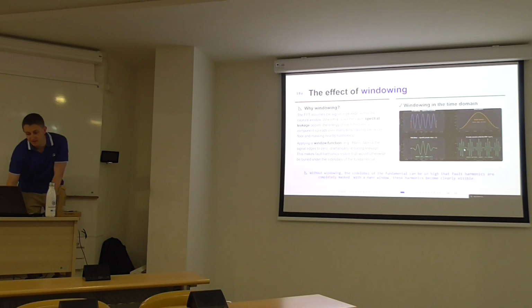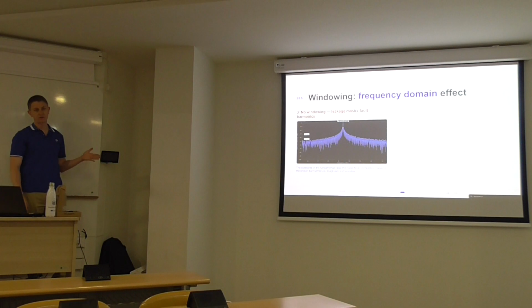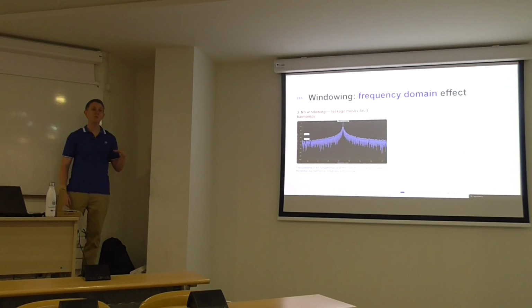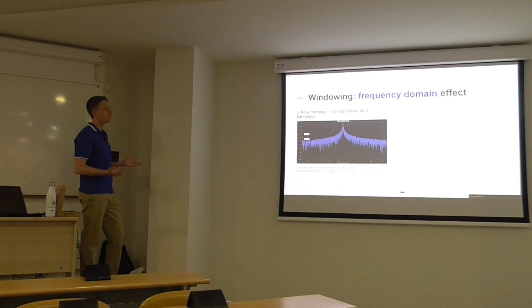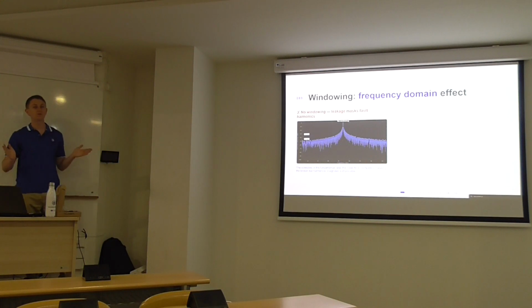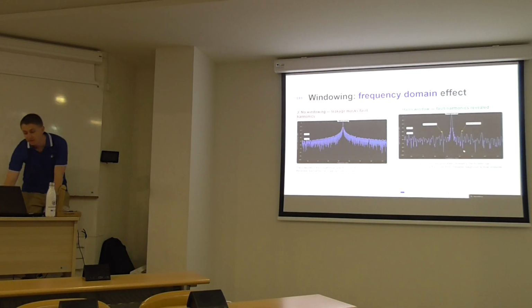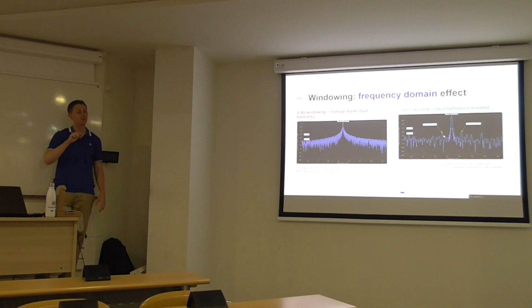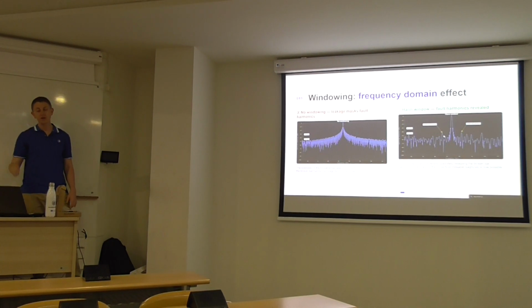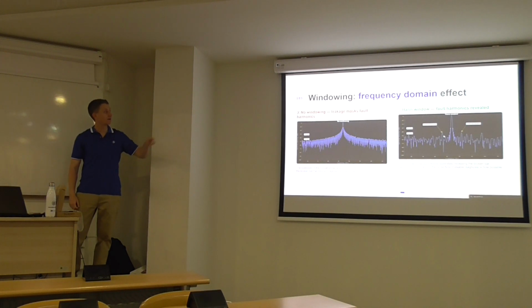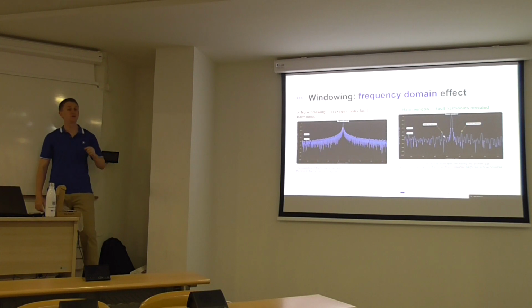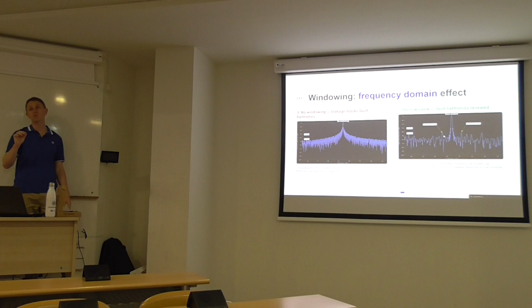So let's see this with a real example, okay? This is a real motor that we measured a couple of weeks ago. First of all, we take the FFT without the window. And apparently, there is nothing wrong with this motor. We just see the fundamental component, but we don't see any sidebands. For me, now the motor is healthy. However, if I now apply the window, I can clearly see the broken bar harmonics. And in this case, they are above the threshold at which we start considering that the motor may have a broken rotor bar. So it's super important. If I had not applied the Hann window, I would consider that motor healthy, when it's not. So it's always important to apply this window.